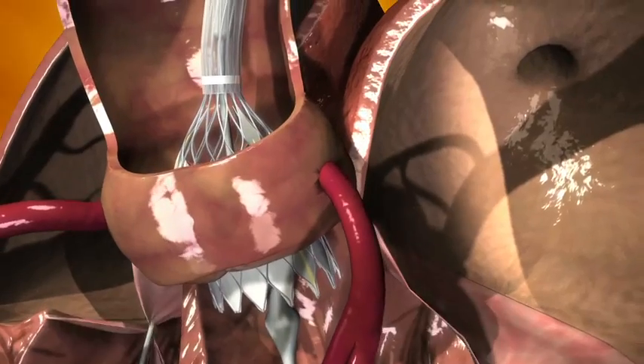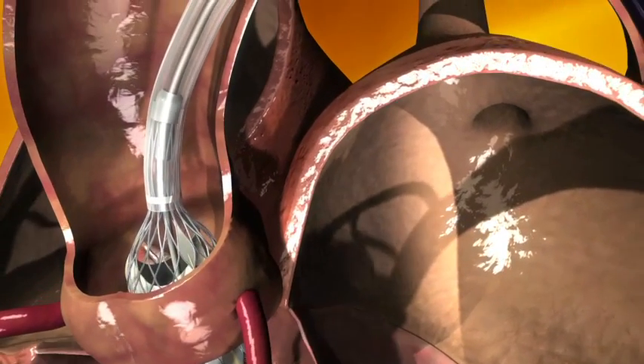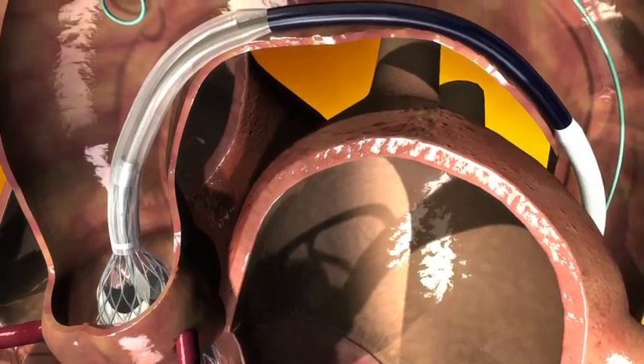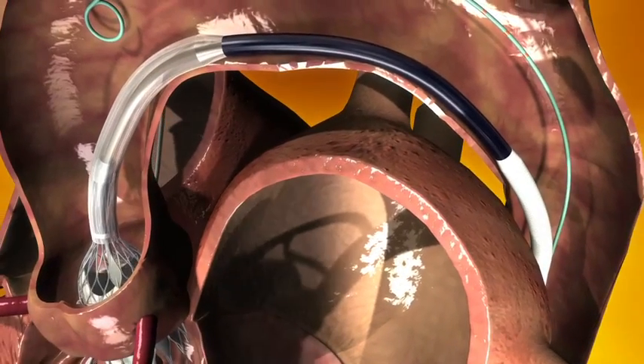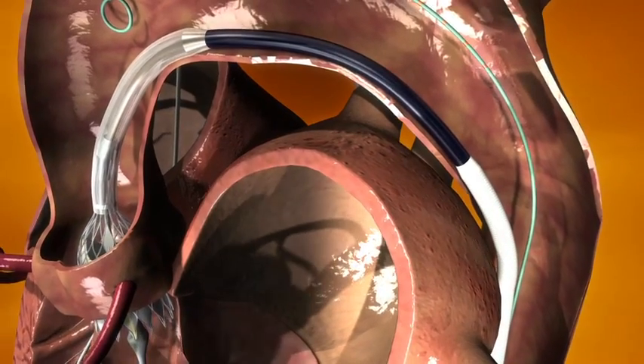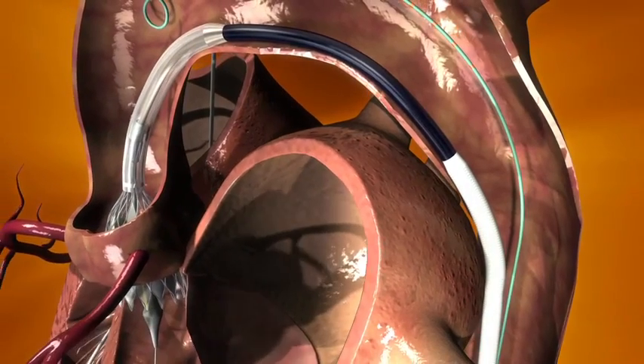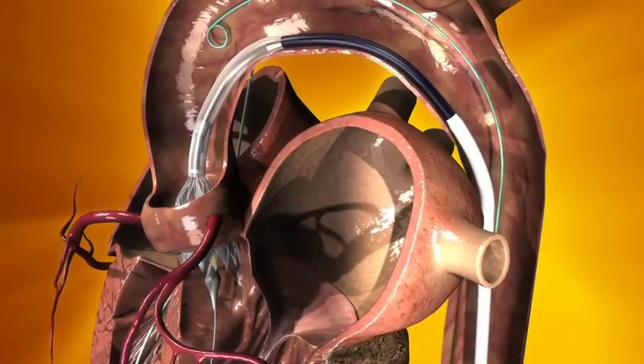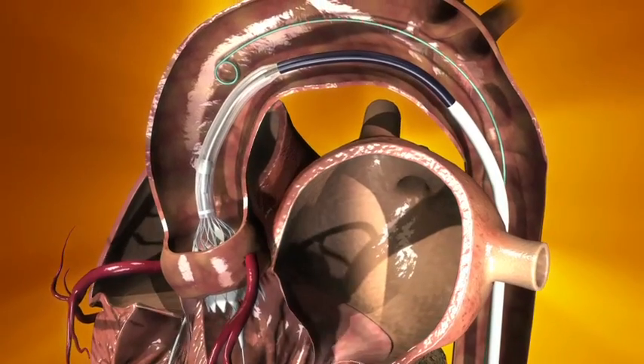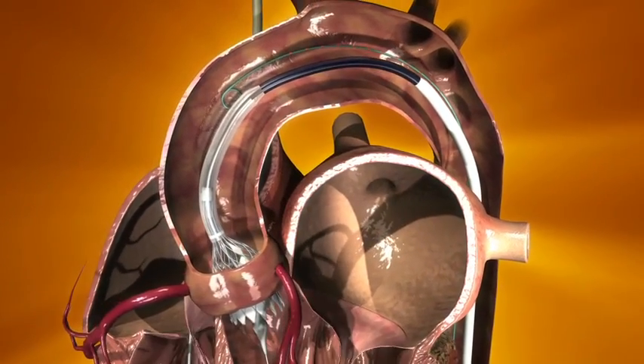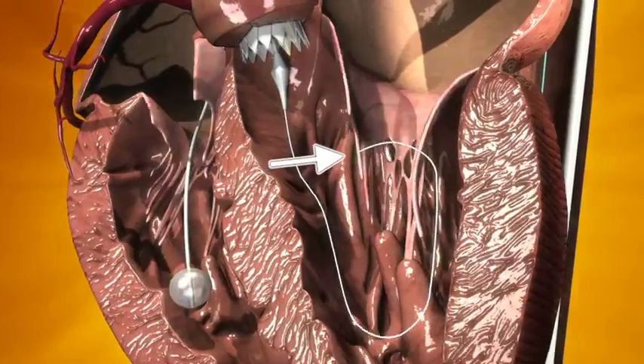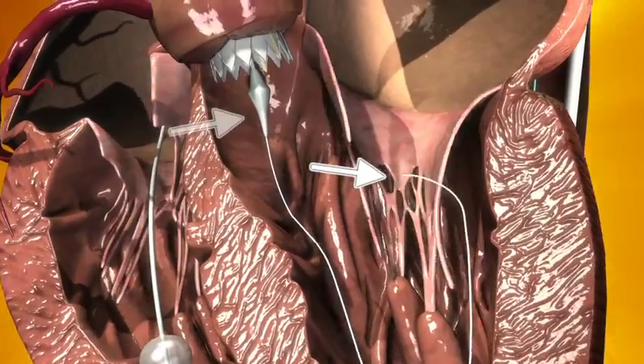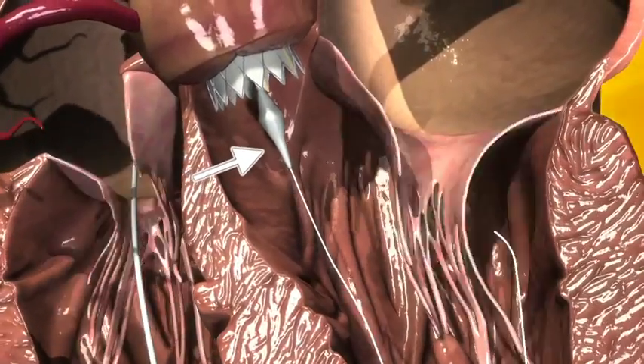When satisfied with valve placement, observe the catheter position in the arch to identify the presence of tension in the system. If the position of the catheter is along the inner curvature of the aortic arch, this may indicate the presence of tension in the system, placing an antegrade force on valve. If tension is suspected, relieve the force on the valve by slightly pushing on the catheter just prior to valve release, and retracting the guide wire until the distal tip of the delivery catheter centers inside the inflow aspect of the frame. Once tension has been released from the system as needed, turn the micro knob until both loops disengage.